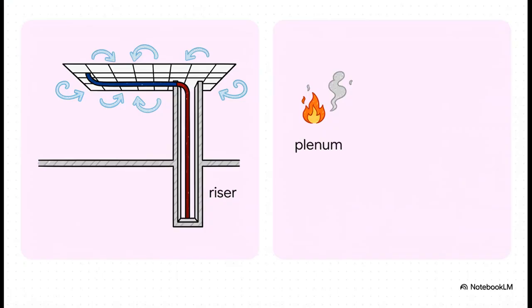Here's one you'd probably never think about, but it could literally save lives: fire safety. Not all cable jackets are the same. If you're running a cable through a plenum space, that's the area above a drop ceiling that's used for air circulation, building codes require you to use special plenum-rated cable. Why? Because in a fire, this cable is designed to burn slowly, and more importantly, to not release toxic smoke. This prevents the building's own HVAC system from accidentally spreading poisonous gas everywhere.